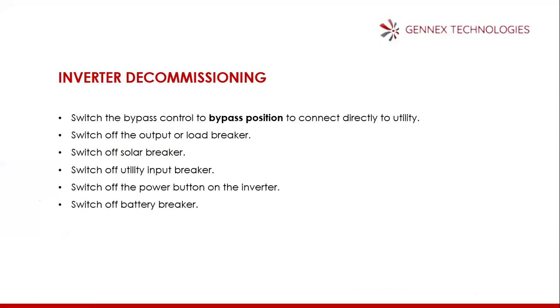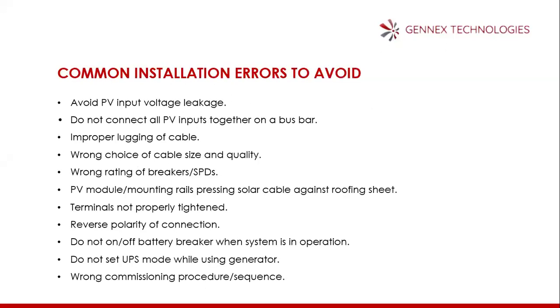You can follow the sequence. Switch off the power button on the inverter. Then finally, you switch off battery breaker. Please be careful. It is the battery breaker that will go off last. This is important. Common installation errors to avoid.